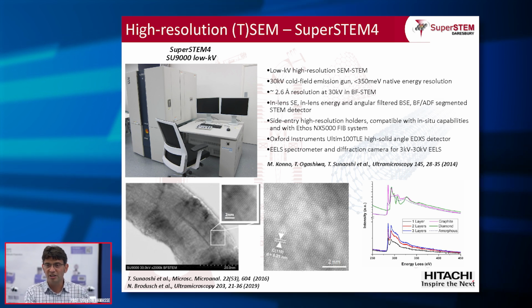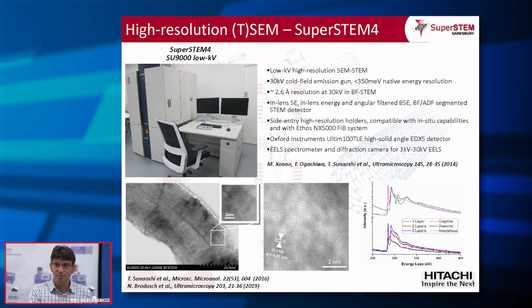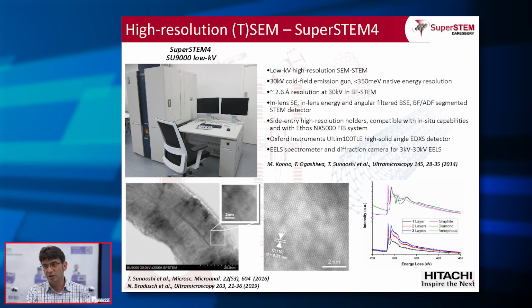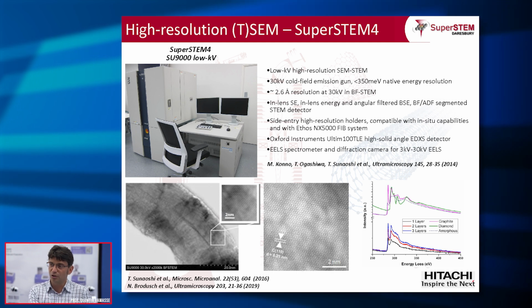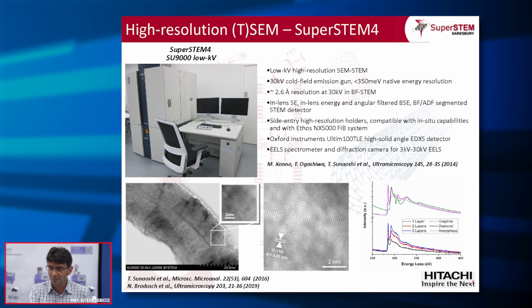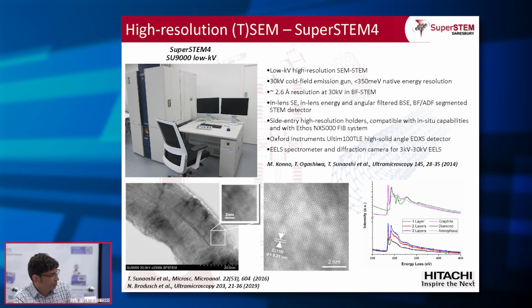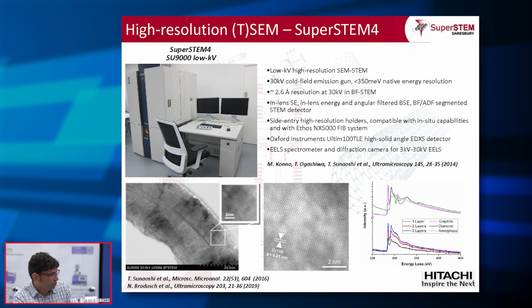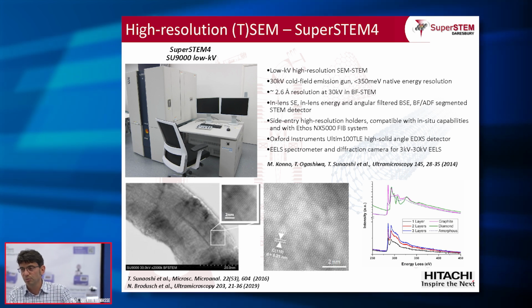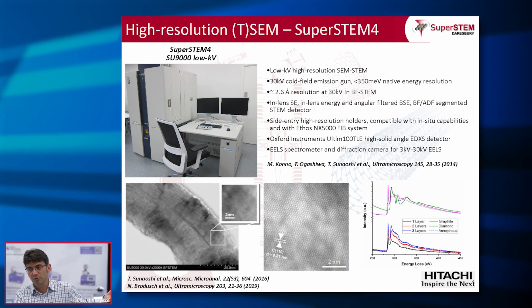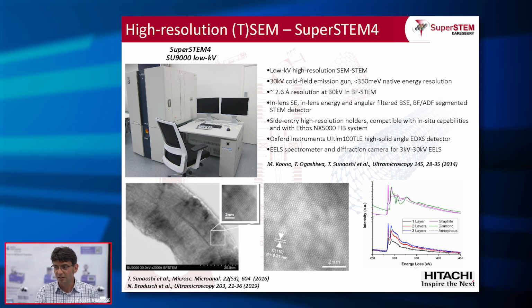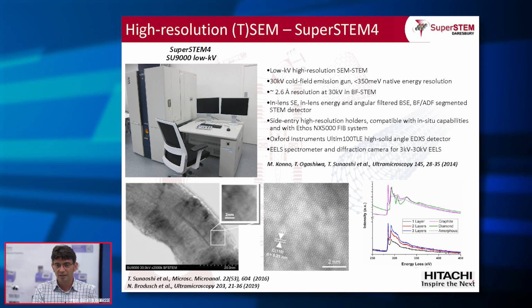I'll show you images that are not bright field, but high angle annular dark field STEM, and for those, the only trick is a little bit of help from channeling through the crystal, but otherwise none of that CTF playing around. That's a multi-wall carbon nanotube, again in the same instrument, showing the 2.3 angstrom and 3.5 angstrom spacing of carbon. These are from this machine, at 30 kV.